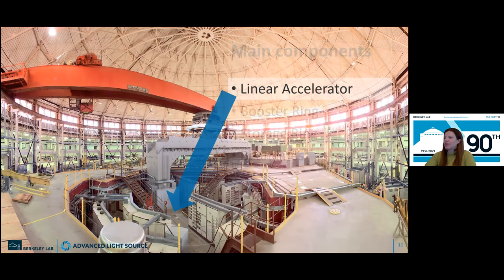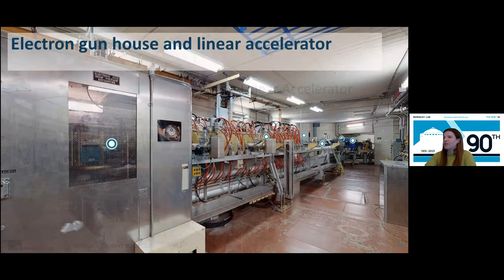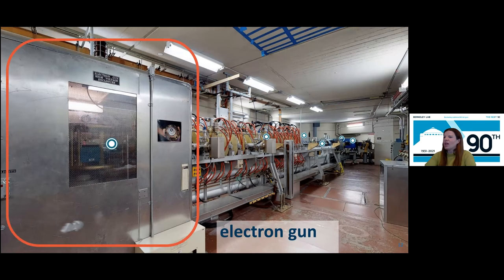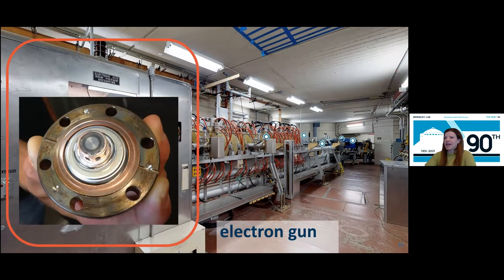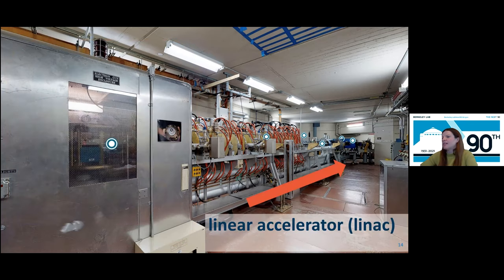So we'll go into the little bunker room where we produce the electrons. It's inside this gun, we call it the electron gun, that you can fit into your hand, where we heat up this tungsten metal to over 1,000 degrees Celsius, and we boil off the electrons, then accelerate them in a line, so that's why it's called a linear accelerator, into the booster ring.